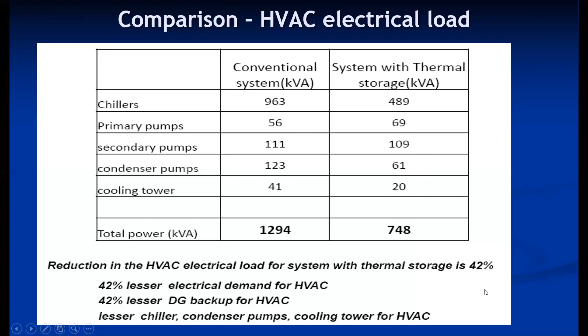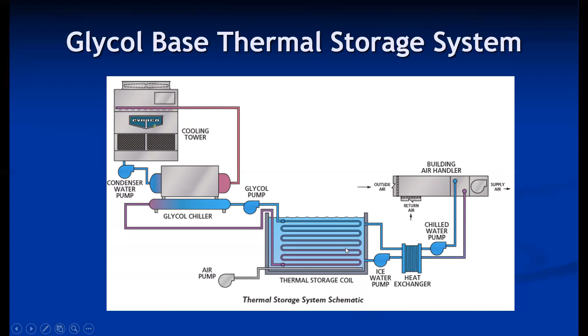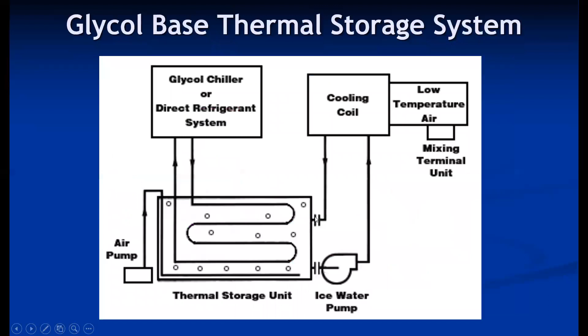Now these are some different models of thermal storage system. In this particular model, the chiller mainly produces glycol, and the glycol is circulated through a thermal storage coil tank, where it produces either ice or icy water, and that icy water is circulated to the AHU chill water coils. Depending upon the energy requirement, it extracts the chill water, and the remaining chill water is stored here. So a separate glycol system is used. Different configurations are there. This is the same diagram in a simplified version.